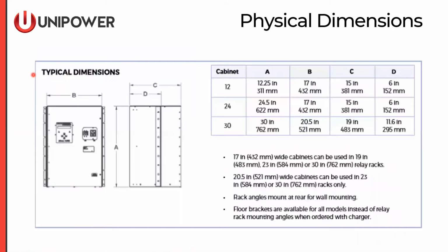Next slide, please. So typical dimensions, we have 3 different cabinet sizes for the ARR-M series, 12, 24, and 30 inch. 12 and 24 inch cabinets can be mounted in either 19 or 23 inch relay racks, whereas the 30 inch tall charger can only be mounted in a 23 inch relay rack. All chargers can also be equipped with the standard wall mount brackets or floor mount brackets. If floor mount brackets are ordered, you have the option of also ordering with an optional drip top. Next slide, please.